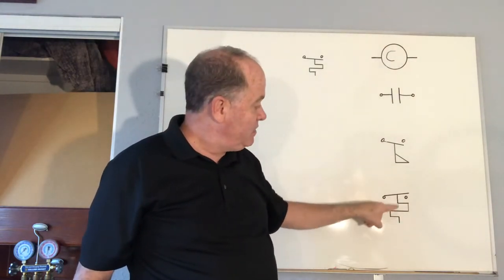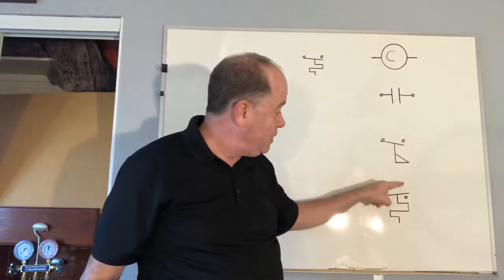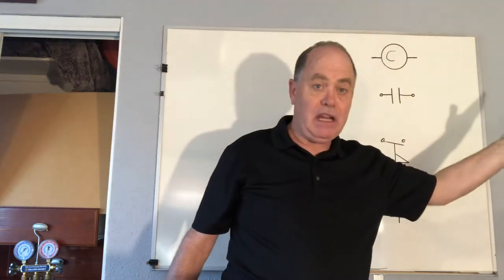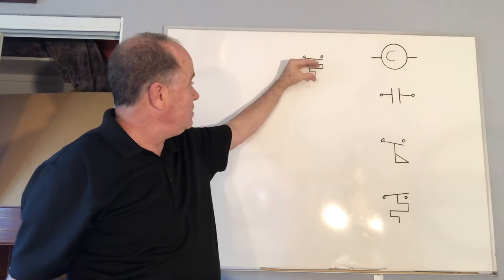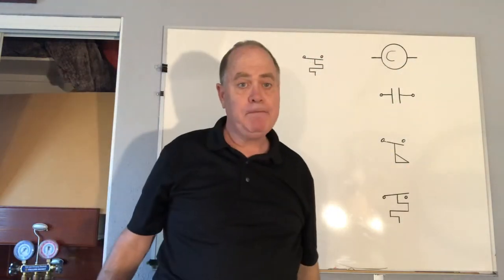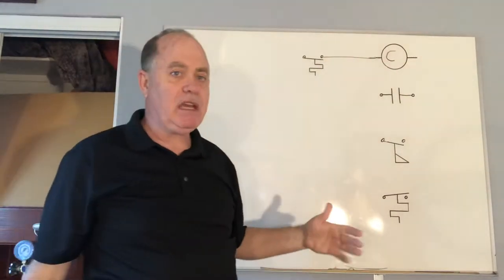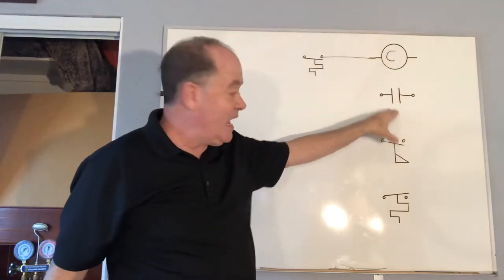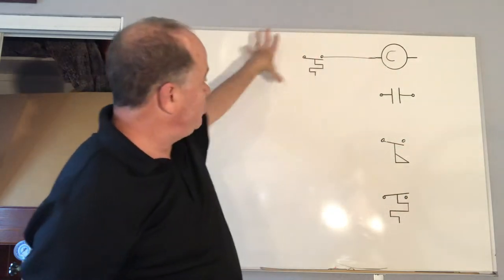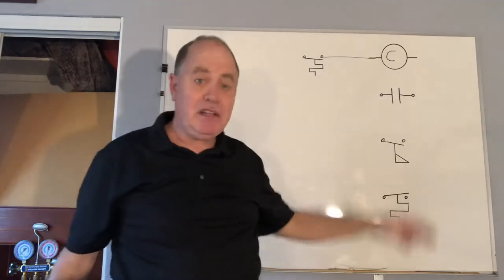This is a heating thermostat, representing a bi-metal — brass and steel together. When it gets cold it contracts, so when something gets too cold we close the heating thermostat and bring on heat. With a cooling thermostat, you have that bi-metal symbol, and when it gets too warm and expands, you close the contact and send energy down to something like a contactor coil. Generally, the switches, contacts, thermostats, humidistats, and flow switches are drawn on the left side of the diagram, and the electrical loads are on the right-hand side.